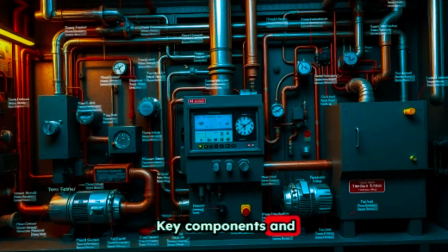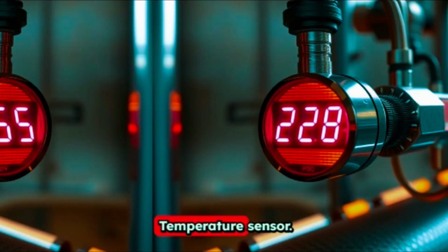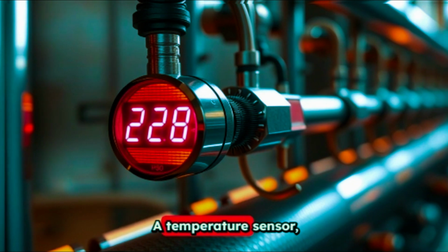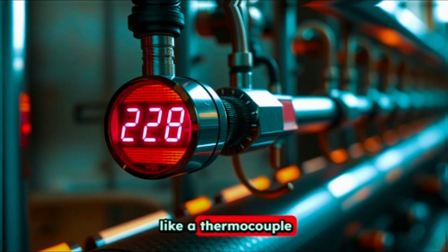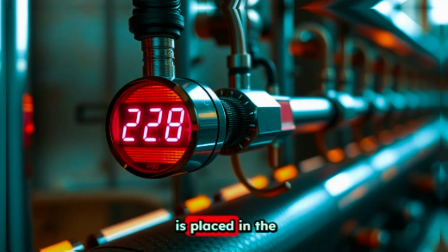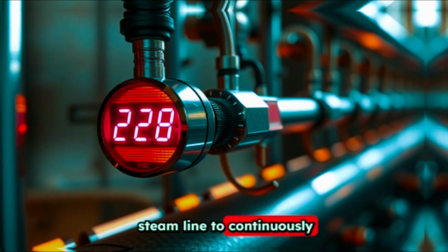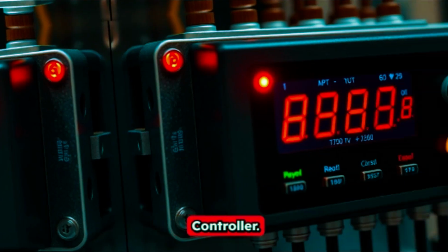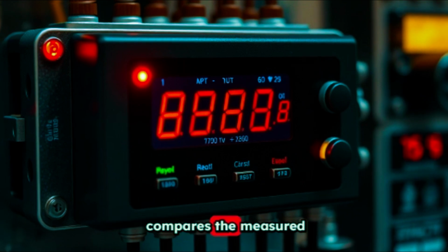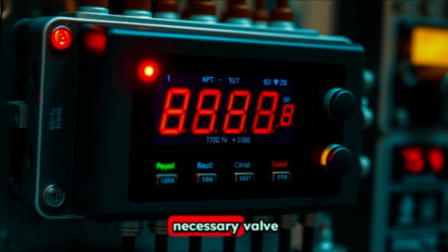Key components and working principle. Temperature sensor: a temperature sensor, like a thermocouple or RTD, is placed in the steam line to continuously monitor the temperature. Controller: the sensor signal is transmitted to a controller that compares the measured temperature to the desired set point and calculates the necessary valve position adjustment.